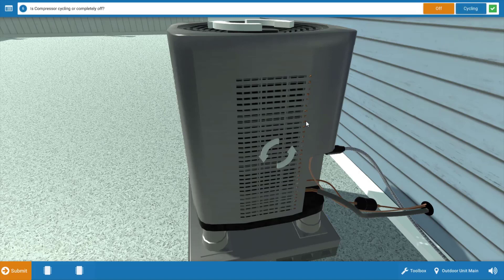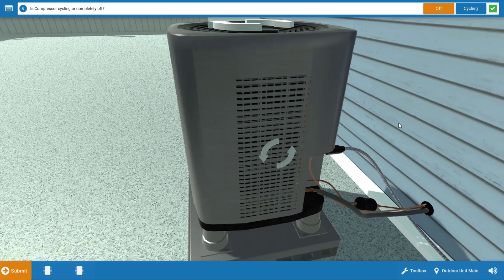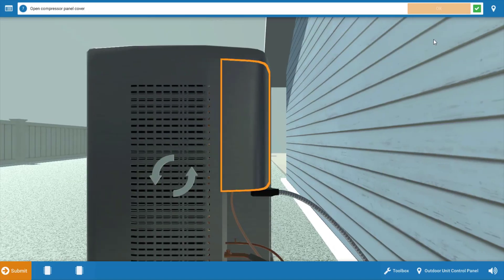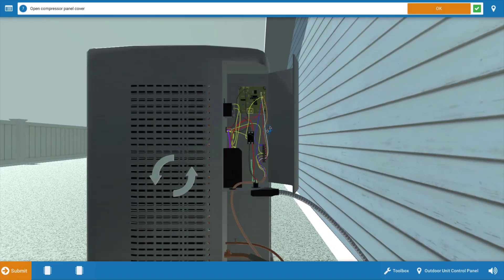Now, is the compressor cycling or completely off? Well, it's completely off. If it's coming on and off, the arrows would spin and then they would stop. And if you had your amp meter hooked up, you'd actually see a brief period of time where you had a current draw and then it would go to zero as it turned off. But it's completely off. So we're going to click off on the procedure guide and we're going to open the compressor control panel.